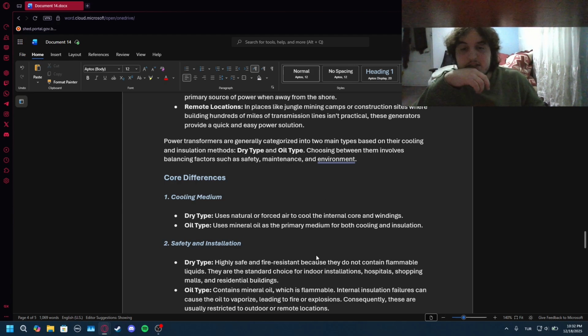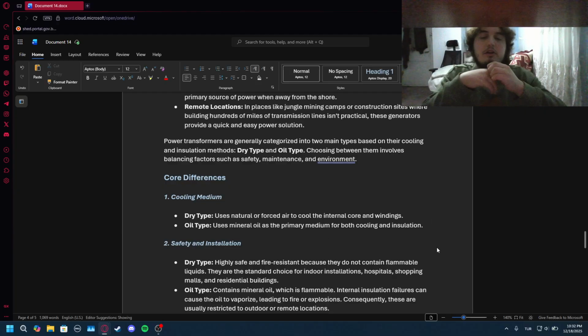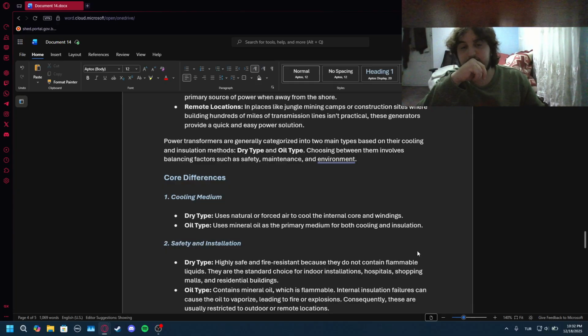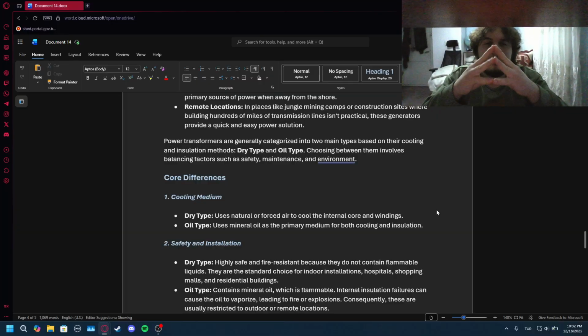Safety and insulation. Dry type is highly safe and fire resistant because it does not contain flammable liquids. It's air. They are the standard choice for indoor installations, hospitals, shopping malls, and residential buildings. Oil type contains mineral oil, which is flammable. Internal insulation failures can cause the oil to vaporize, leading to fire or explosions. Consequently, these are usually restricted to outdoor or remote locations. Here's the deal. An oil type transformer is really simple, and it is more efficient, and it is better. Also, it's less expensive, so it's cheaper.